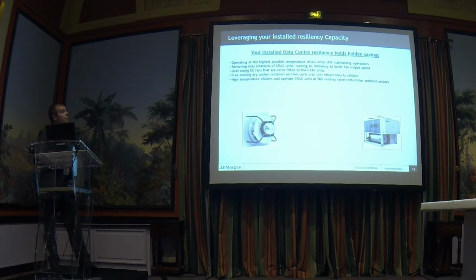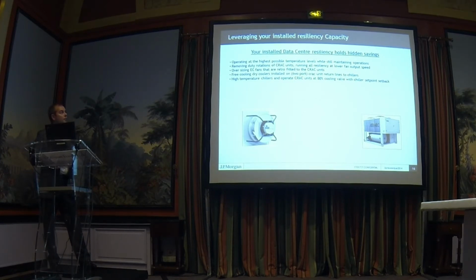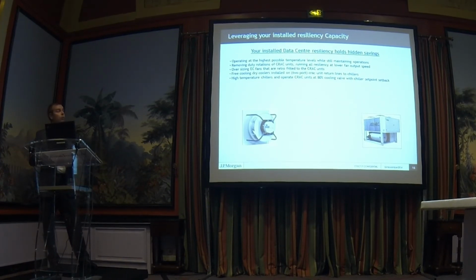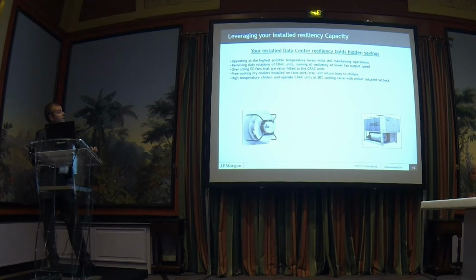So your installed data centre resiliency holds your hidden savings. Operating all your plant at a minimum, especially CRAC units, run them all, the chilled water, back the fans down. If you run half of your CRAC units or a third of them off, you're going to have to run the fans higher. Cube law, twice as fast, 4 times the amount of energy. So operating at highest temperature, remove duty rotations of your CRAC units if they're chilled water. Oversizing EC fans that are retrofitted to CRAC units.